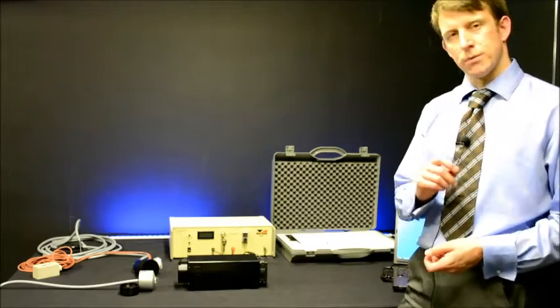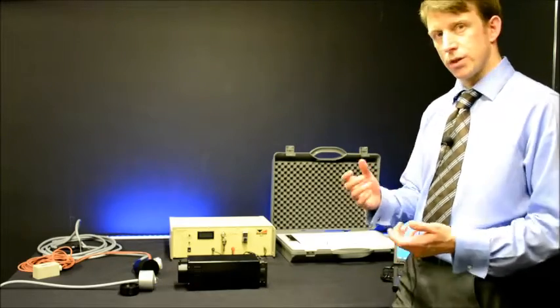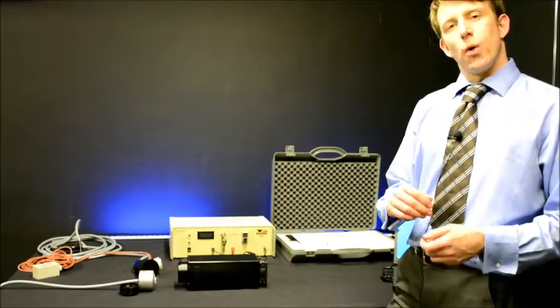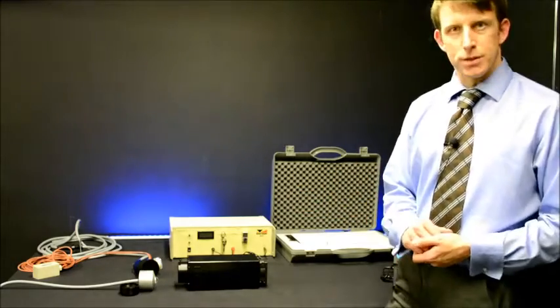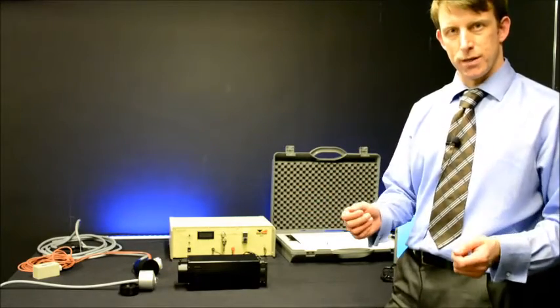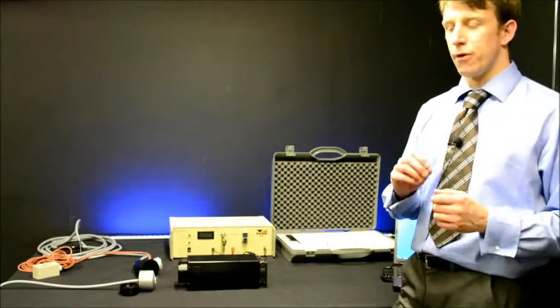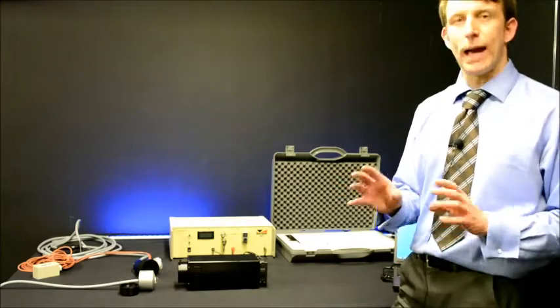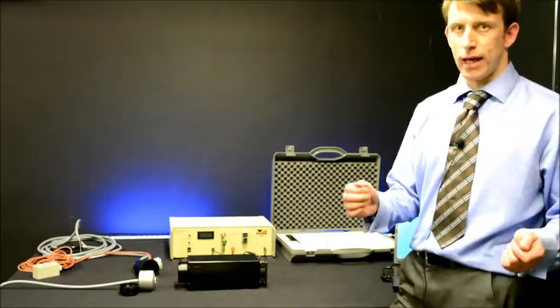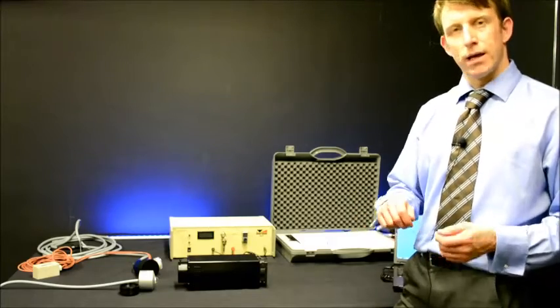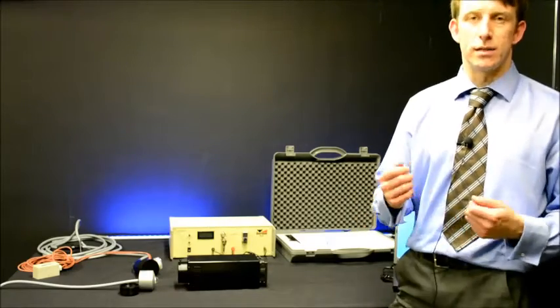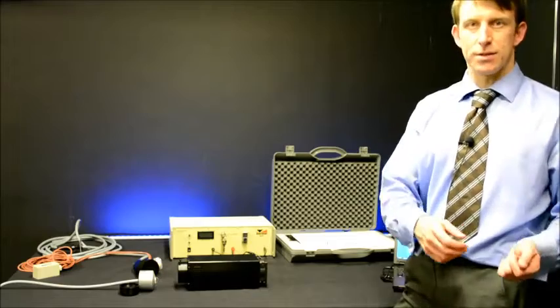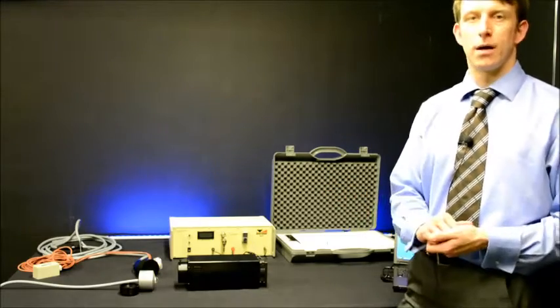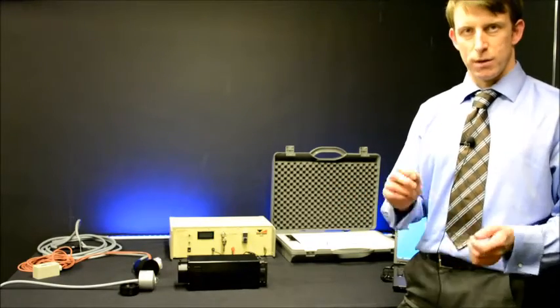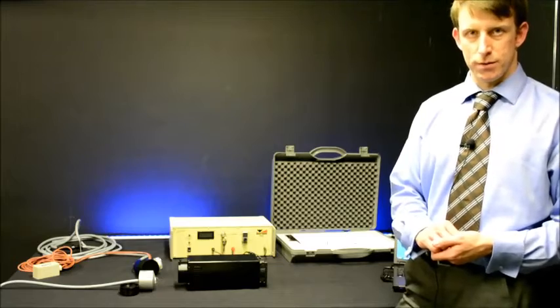One of the main aspects one should consider in using the systems is that, having assembled the spectral radiometer, input optic, etc., one would prefer not to dismantle any of the elements in order to calibrate. Since, for example, were we going to place the fibre in a slightly different position, having calibrated the system and going to do irradiance measurement, there may be some discrepancy in the measurement results.